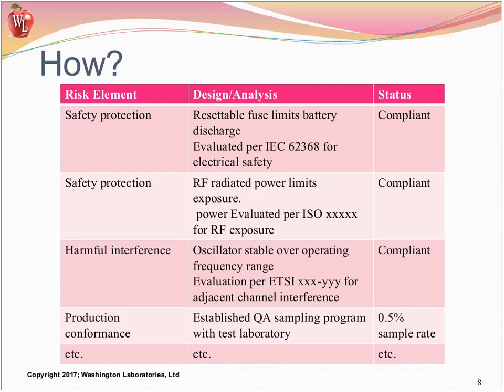Say you have a battery, and somehow the test laboratory didn't realize that you had a backup battery system, and they put in their column of batteries none. Then they're going to have a gap, because the reviewer says you've got a battery, and the safety lab says it doesn't exist. So that's a discontinuity that you need to consider. And that's not your risk. That's something you use to mitigate risk, so it's got to cover it. And the reviewers are kind of particular about that.